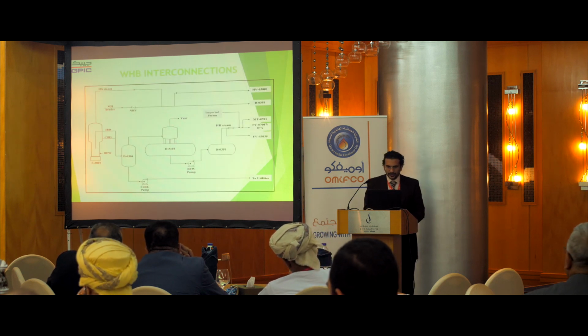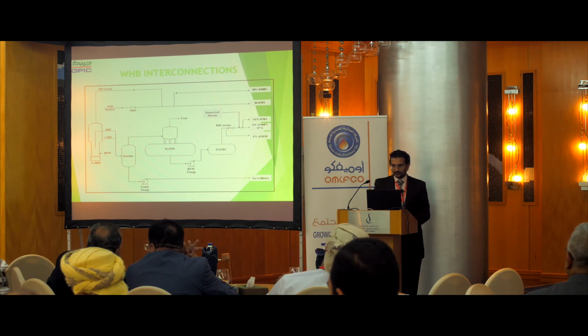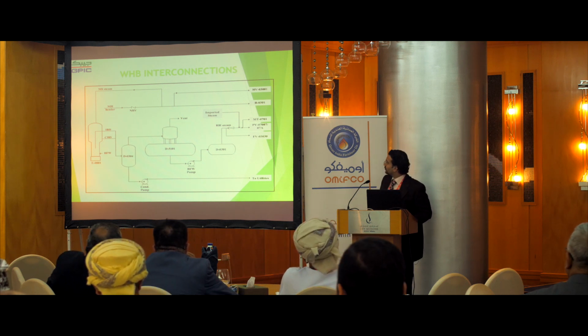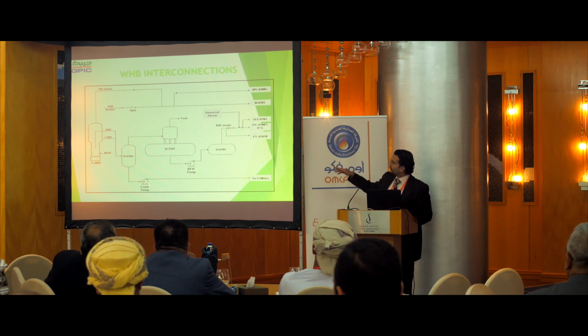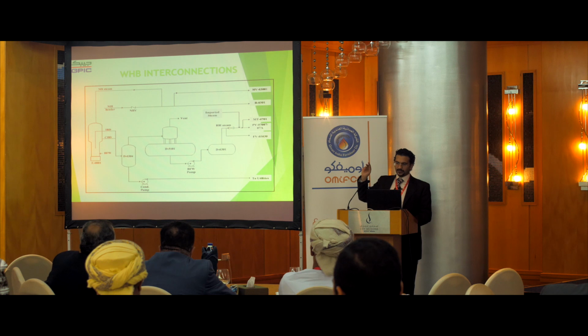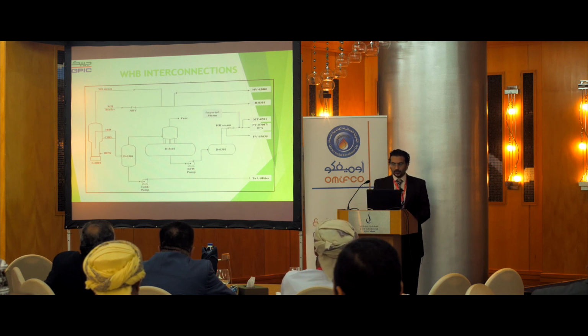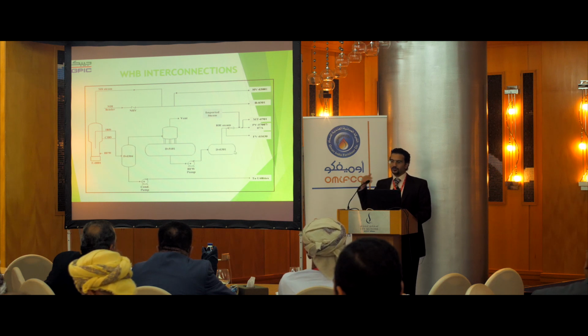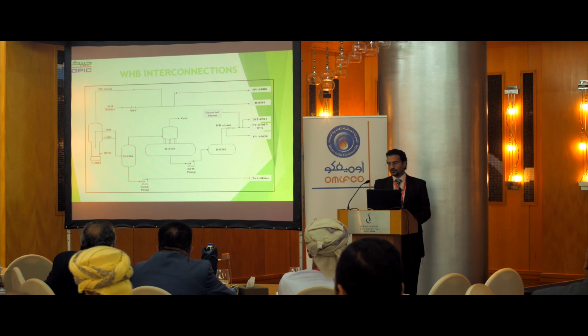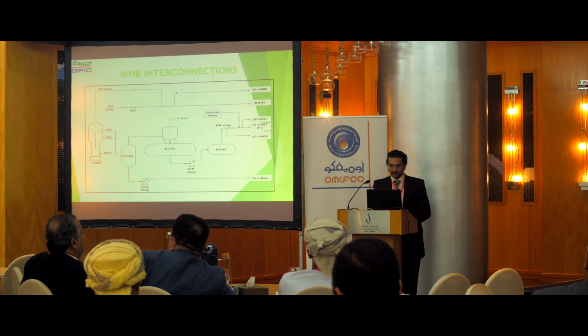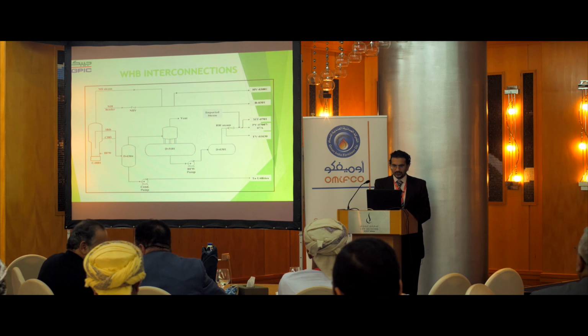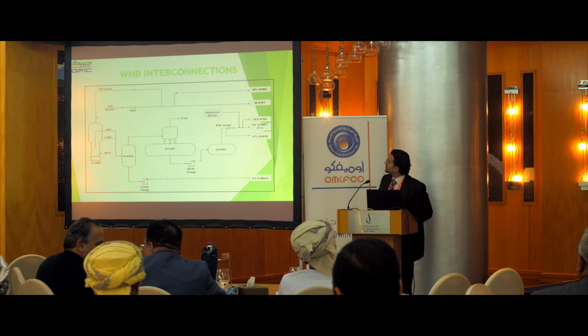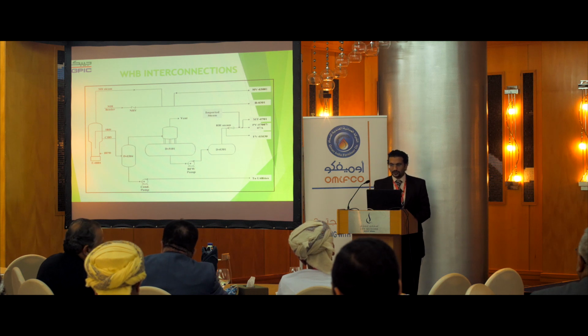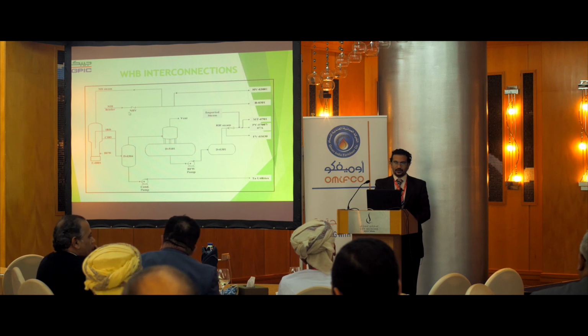So this is our waste heat boiler interconnections. From the deaerator, the water goes down to the boiler feed water pump. Within this pump, we have an intermediate section sending boiler feed water to the waste heat boiler, and the high pressure section goes to our main steam drum that cools down the PG cooler, the process gas cooler, exiting the secondary reformer. Of course, we have our steam coming out of the waste heat boiler going straight to the secondary reformer after mixing with the main medium pressure steam header.